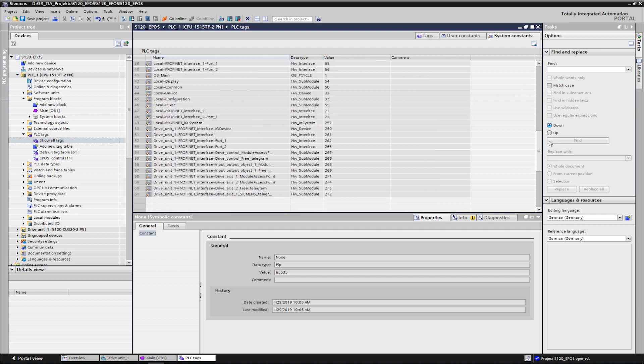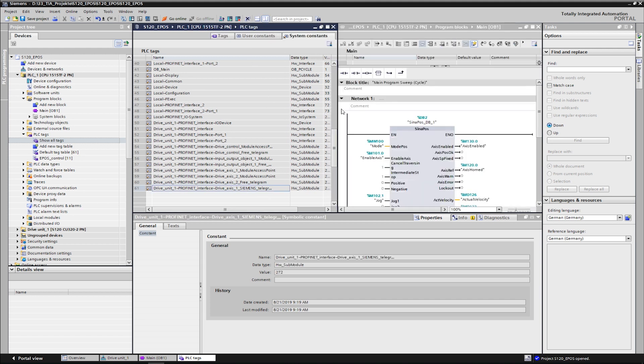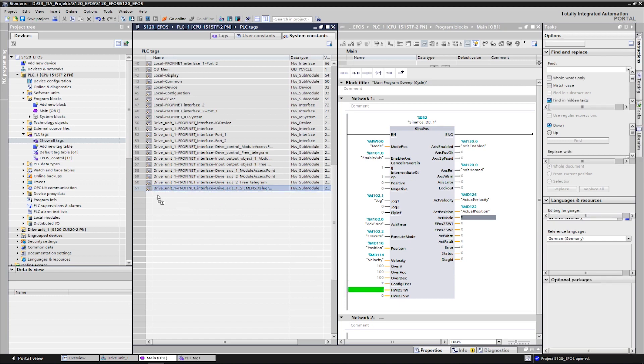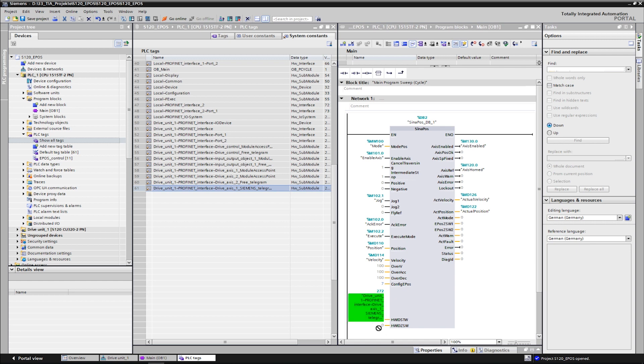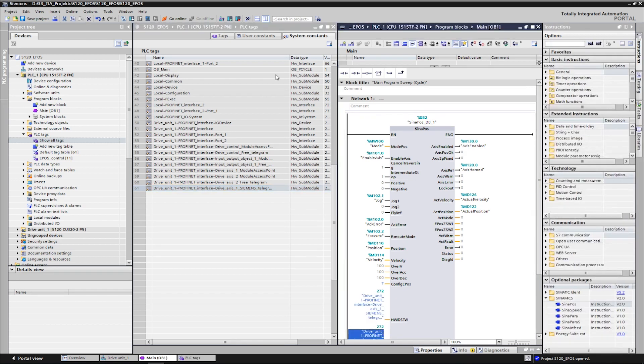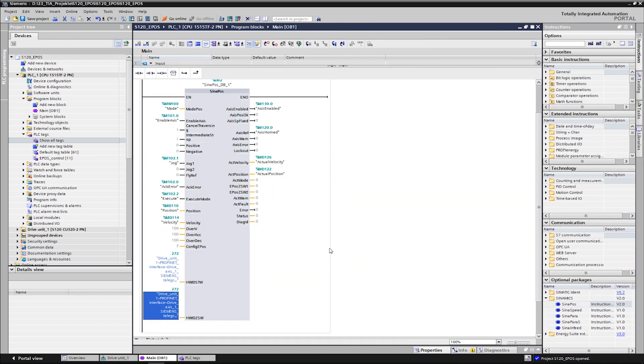From there, we can connect the constants directly to the inputs of the block via drag and drop. The IDs are thereby symbolically addressed. If the inputs for the hardware ID are not correctly interconnected, the block will report an error and cannot communicate with the associated axis.